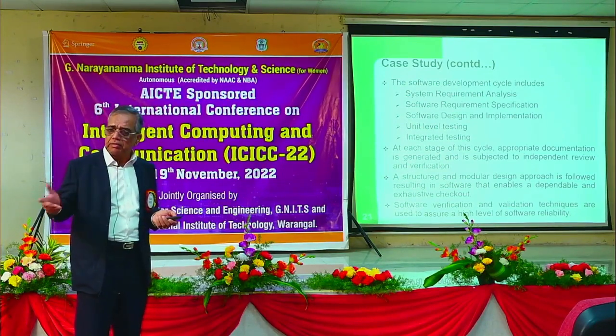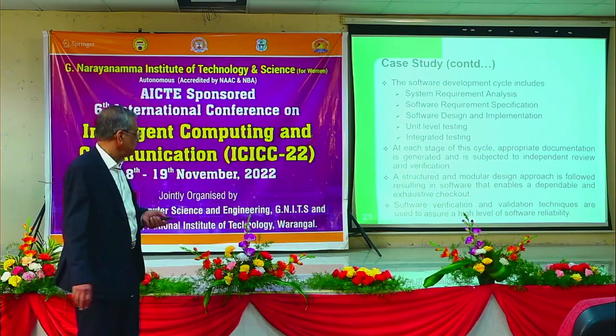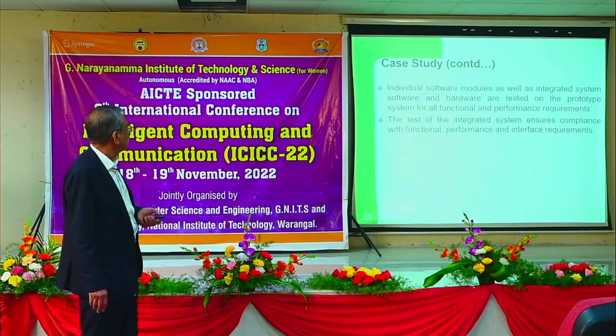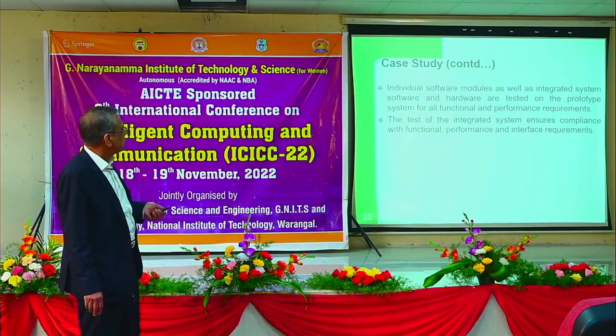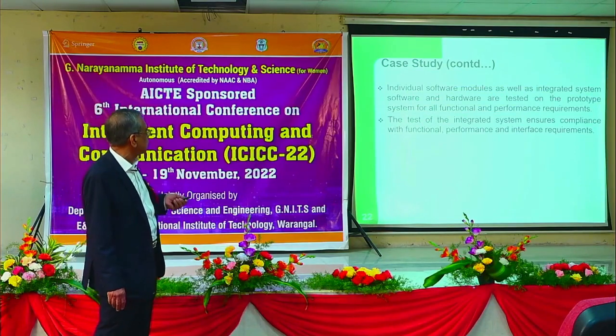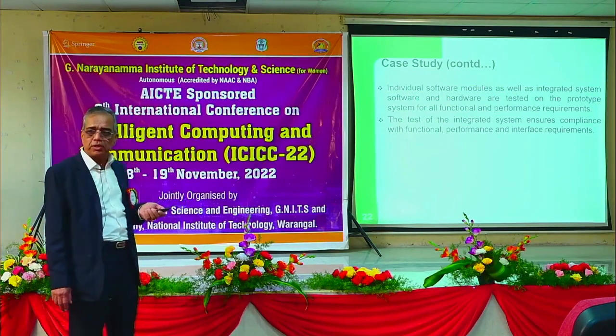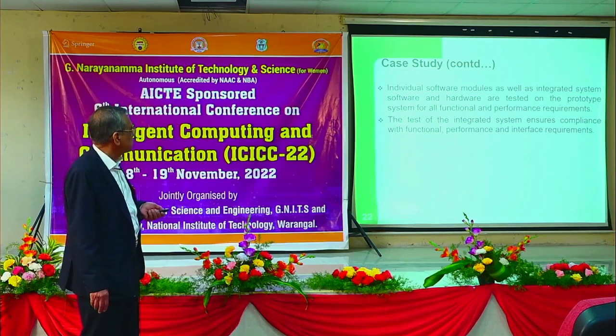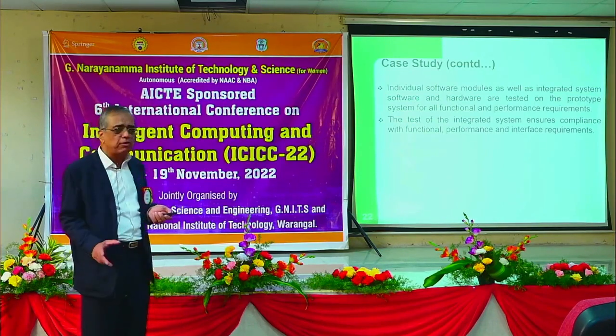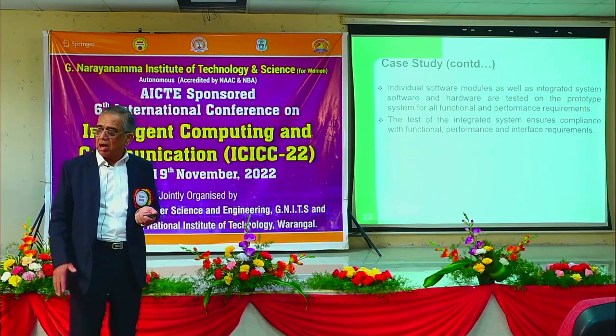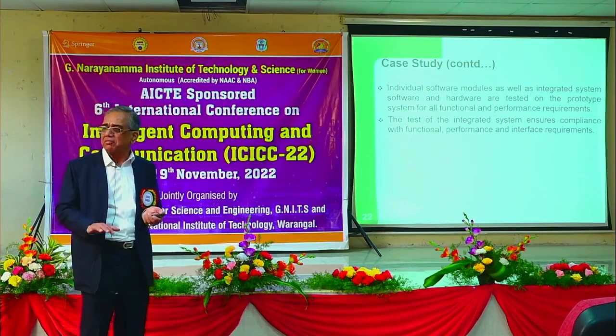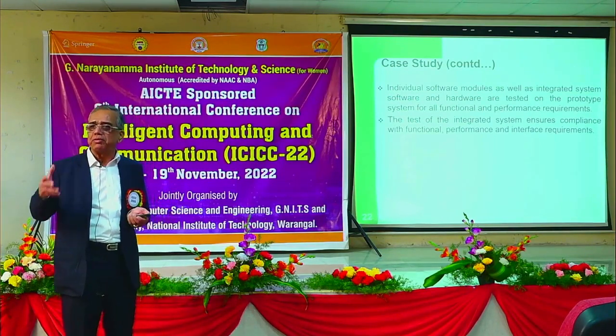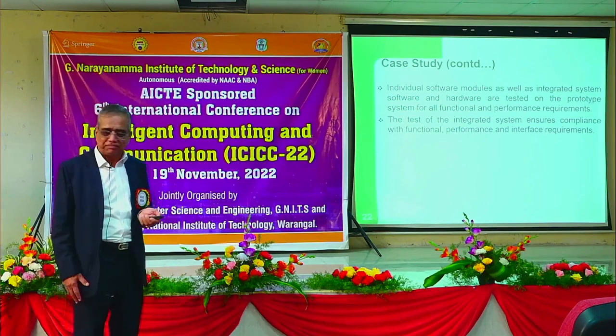Verification is done by an independent team, and validation by loading on the hardware, prototype hardware. Individual software modules, as well as the integrated system software and hardware, are tested on the prototype system for all functional and performance requirements. The test of the integrated system ensures compliance with functional, performance and interface requirements. Only after full testing, verification and validation is it permitted to be put into the plant.